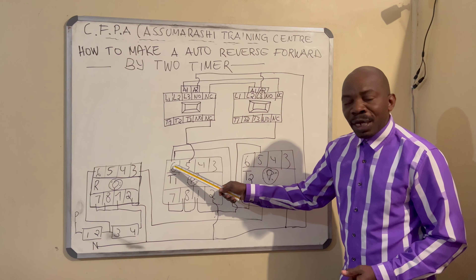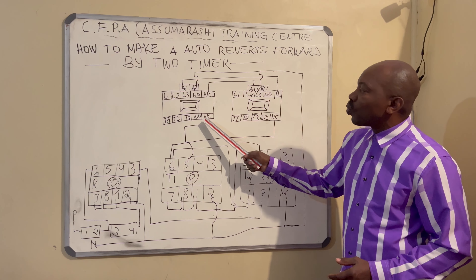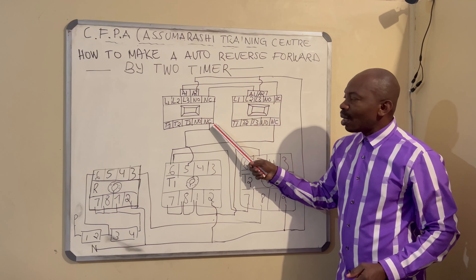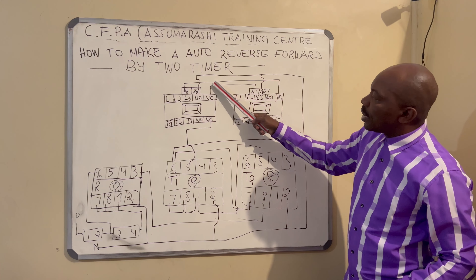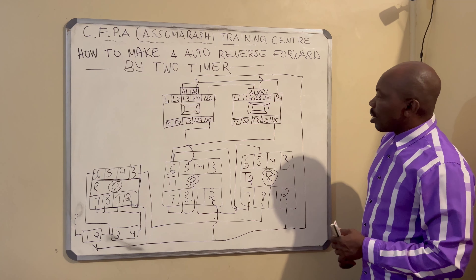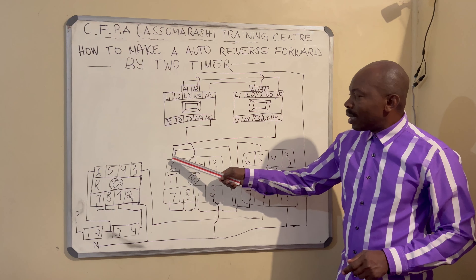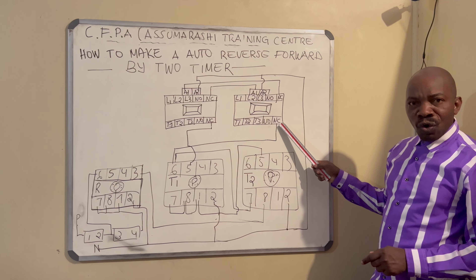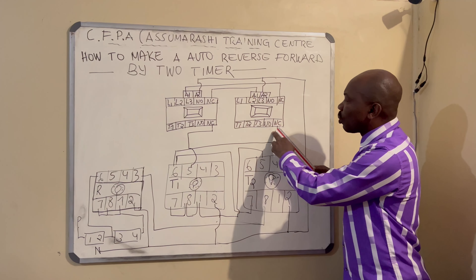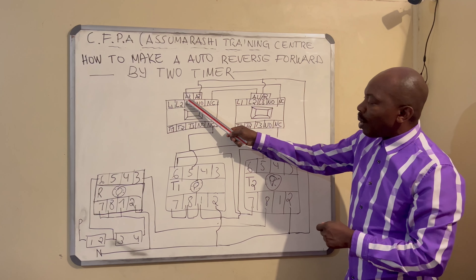Number five, the normally closed terminal of timer number one, goes to NC. This NC on the contactor is terminal number 22. The NO is terminal 21. This terminal 21 is connected to A1 of contactor number two. After that, you come back to number six of timer one — this number six comes straight to terminal two of contactor number two. Terminal six then goes to terminal 22 of contactor, and 21 goes to A1 of contactor number one.